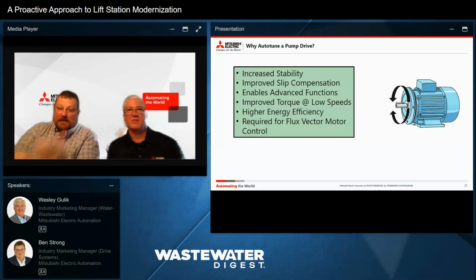Improved torque at low speeds. I recently worked on a pump that had a lip seal for the seal, and it wouldn't actually start in volts per hertz. So we changed it to a flux vector mode, and we created enough torque so it would overcome that static friction from the lip seal. So other reasons, it's required for flux vector motor control. So higher efficiency, more accurate control of your motor, all good things.